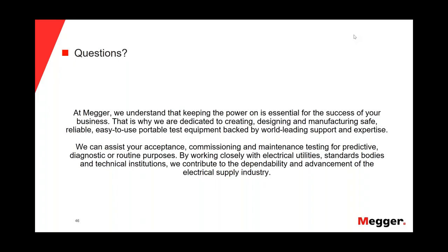And to add to that, if you don't mind, that's where the tan delta would give you an indication of a sheath, because if the sheath is torn and water has gotten in, just as in the tables we use during the tan delta, you will see that there's wet cable. And then, of course, like you said, sheath fault testing.